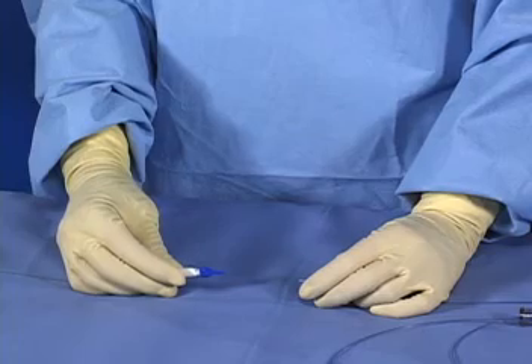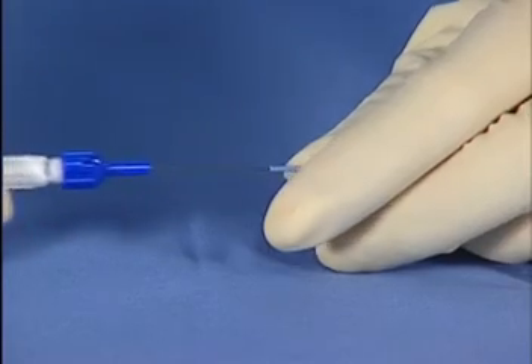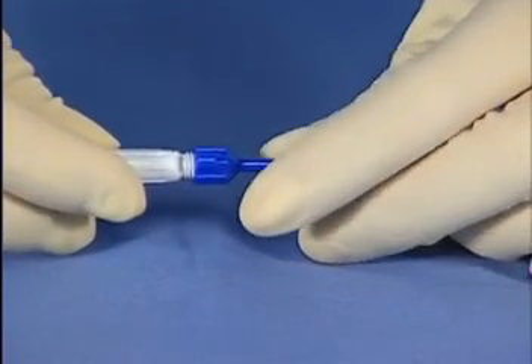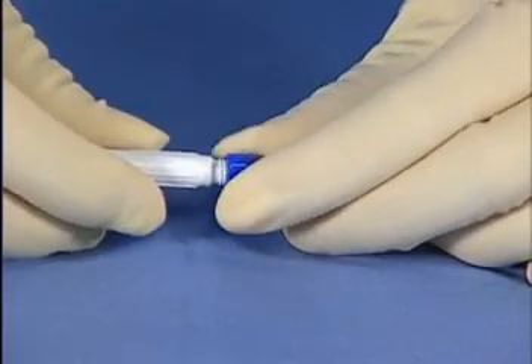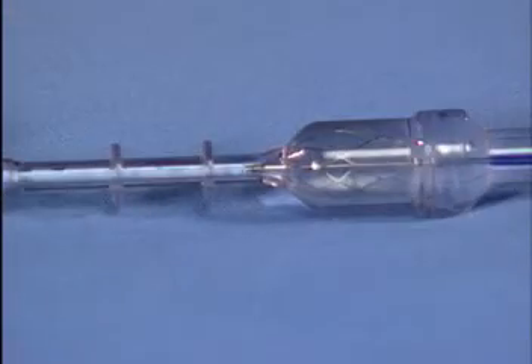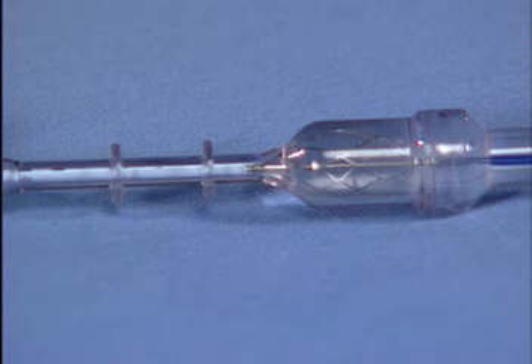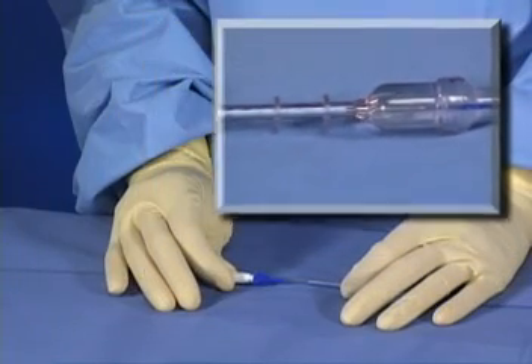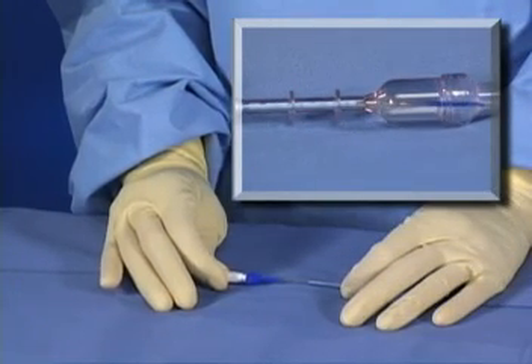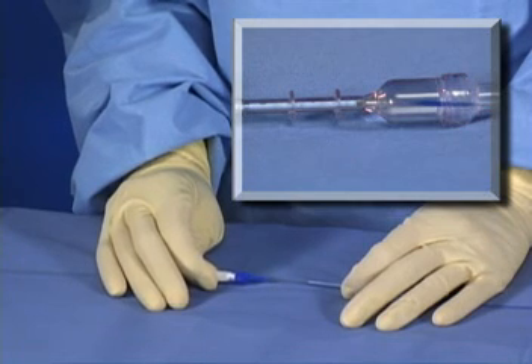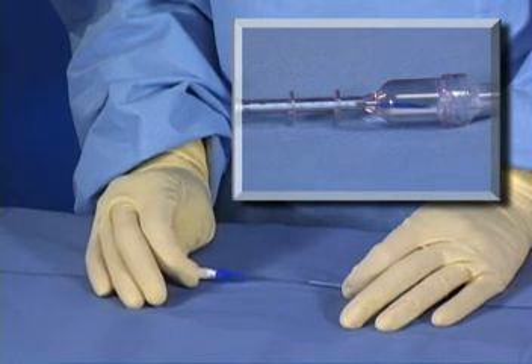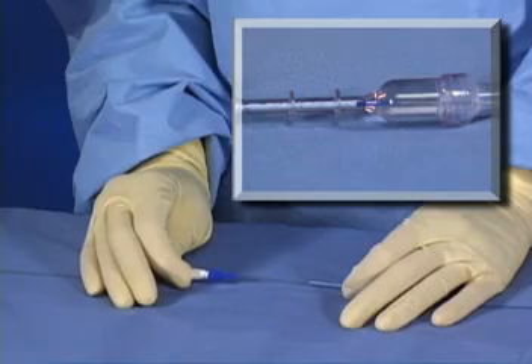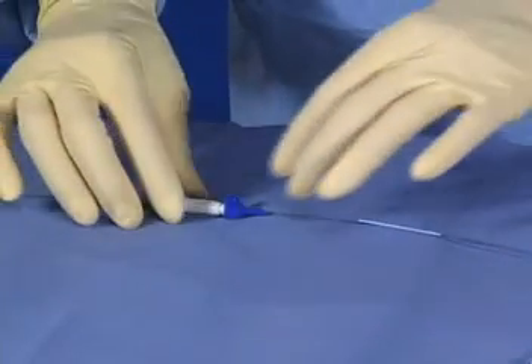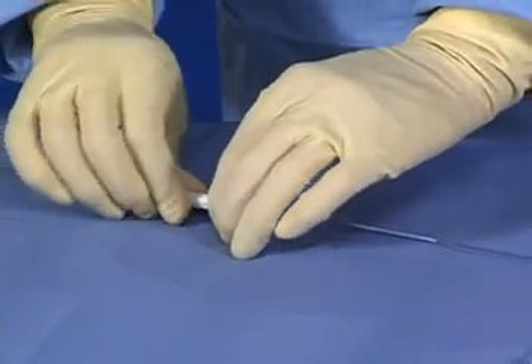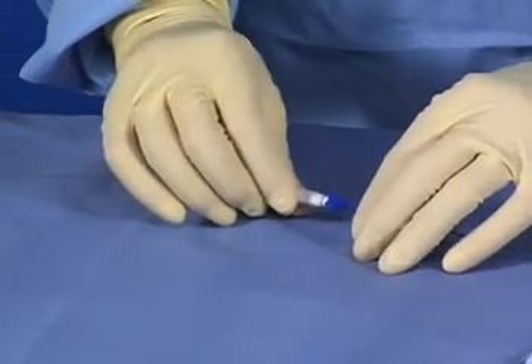Slide the included torque device with the peel-away adapter onto the wire up to the edge of the delivery sheath and tighten. While observing through the flush tool, pull back on the torque device until the filter basket is completely within the delivery sheath. Then reposition the torque device at the proximal delivery sheath edge.